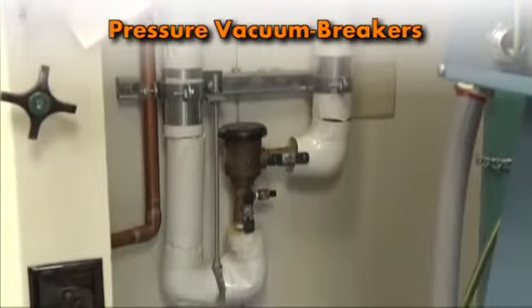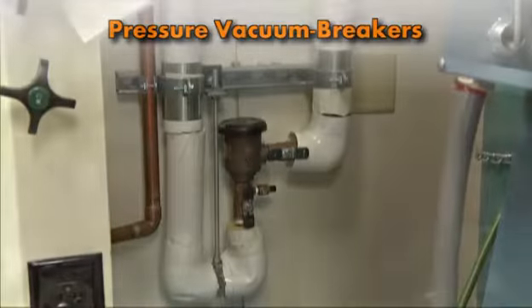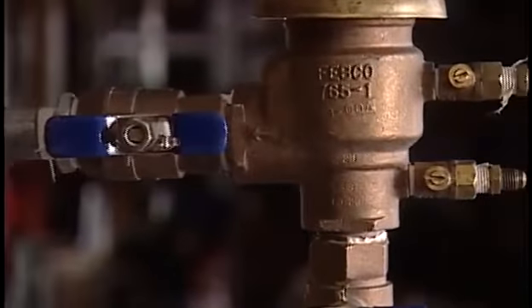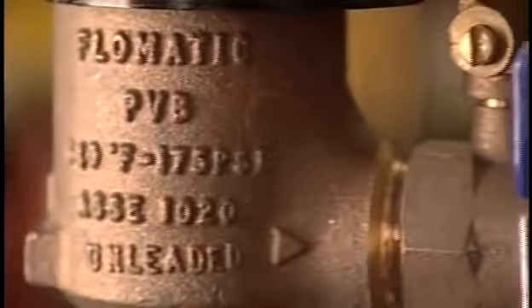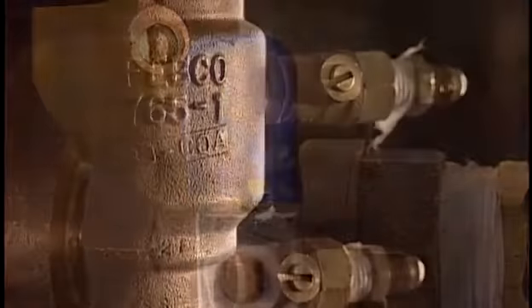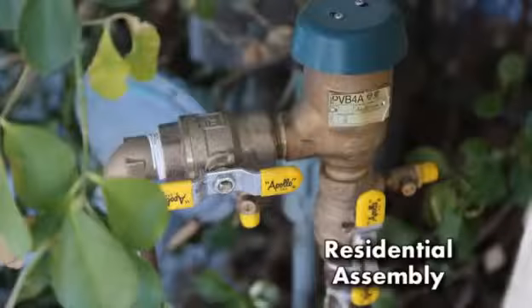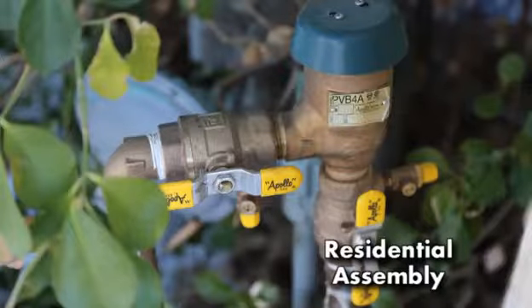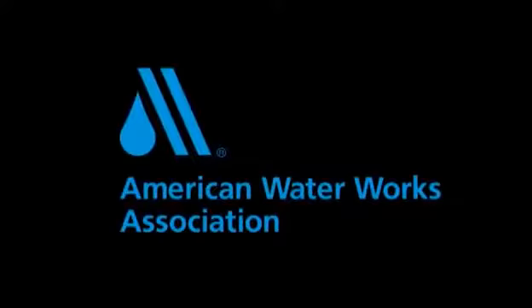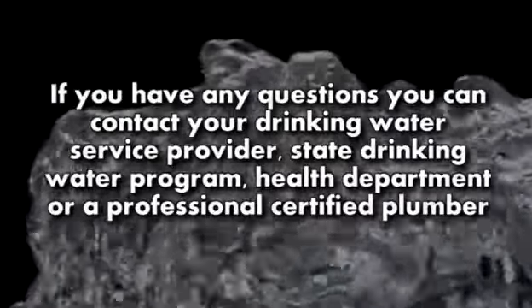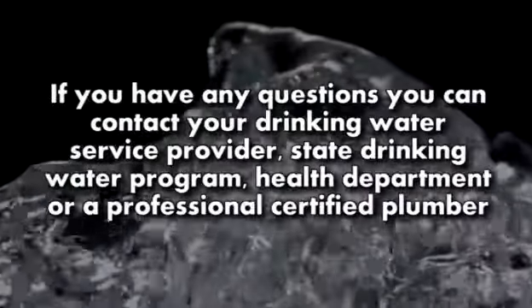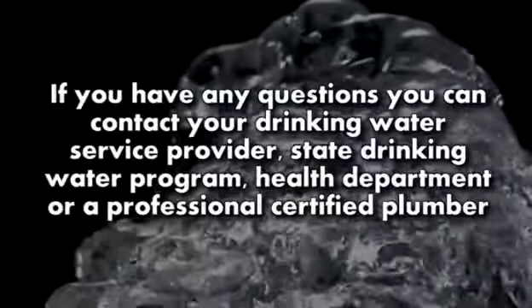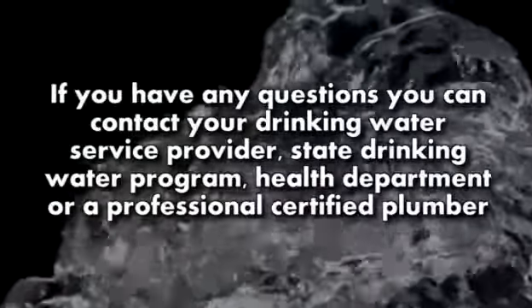Pressure vacuum breakers are designed to prevent backsiphonage or water being drawn back into a water supply when the line is closed. These assemblies should not be used to prevent back pressure. The assembly opens to the atmosphere, thus preventing a vacuum in the line. The American Water Works Association recommends all testable backflow preventers be tested annually. And if you have any questions, you can contact your drinking water service provider, state drinking water program, health department, or a professional certified plumber.